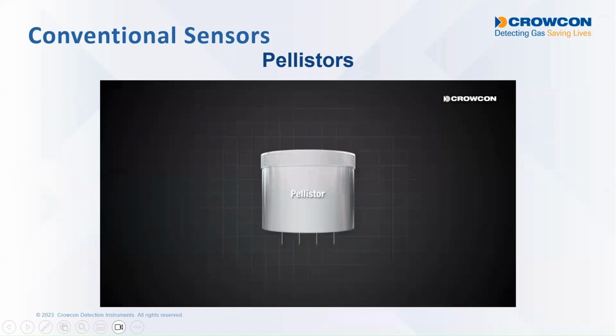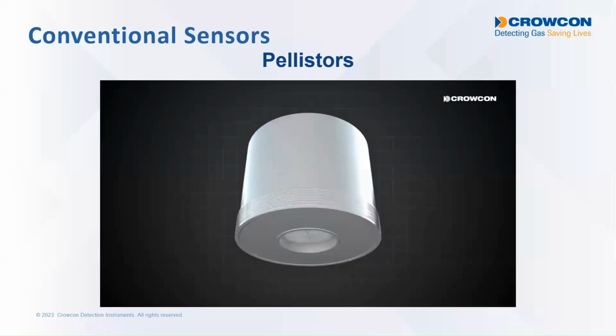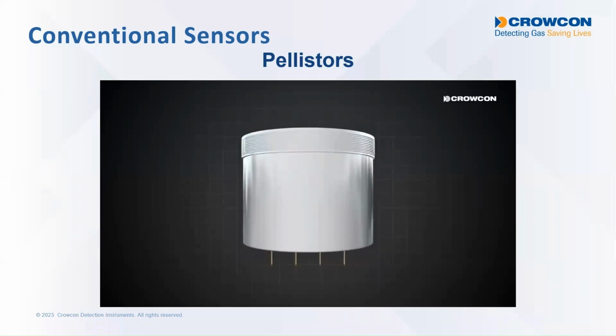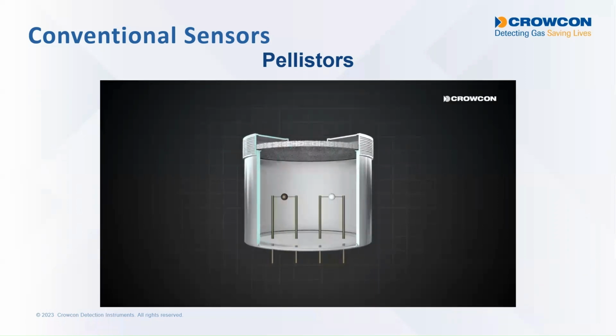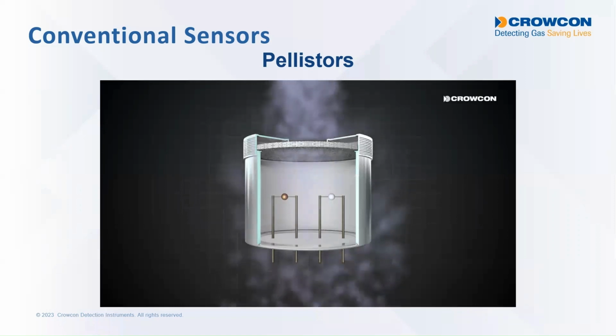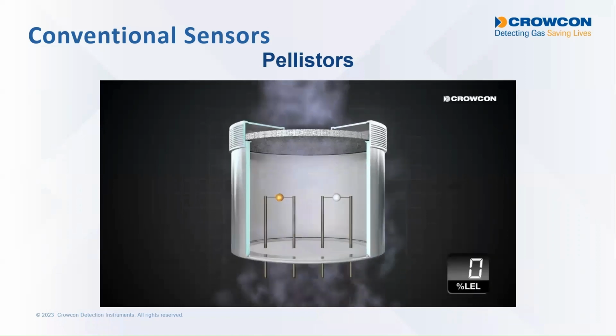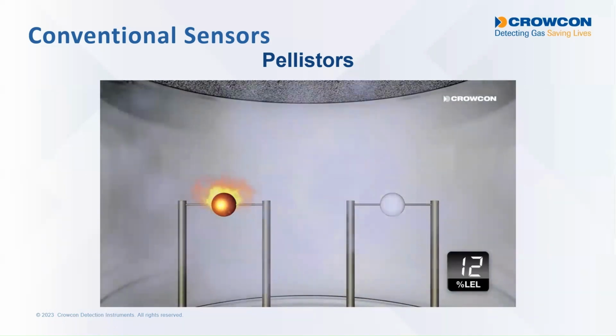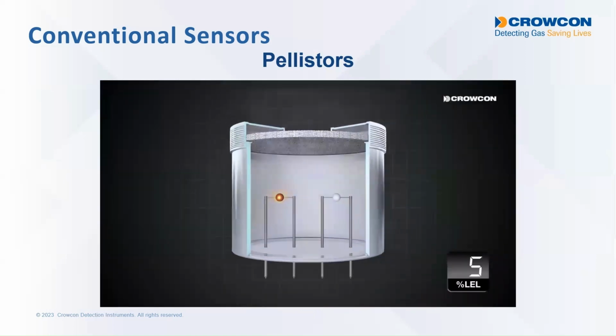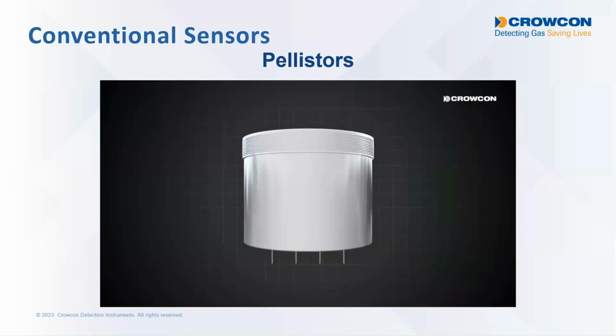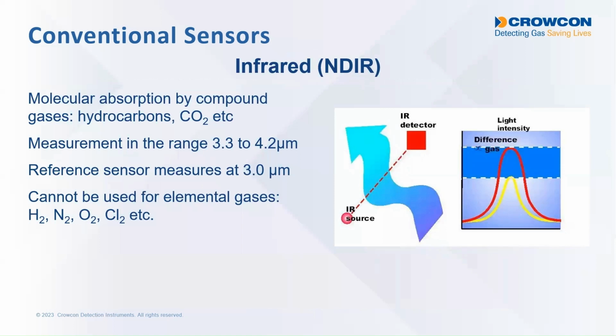So I have an animation here of how the pellistor works. So they're normally mounted in a small can within the instrument. At the top of the can is the flame arrestor, the sinter. It's a porous disc of crushed stainless steel particles that allows gas to permeate through, but will not allow a flame to pass back through the other way. So as I said, the beads are used in pairs. You have an active bead and a reference bead. And as the active bead is exposed to gas, so it burns hotter, its resistance increases, offsets the current flow in the Wheatstone bridge circuit, and we're able to determine the percent LEL gas concentration. So it's a very simple, very direct method of detecting gas and very effective, but it does have some drawbacks, which we'll come to in a moment.